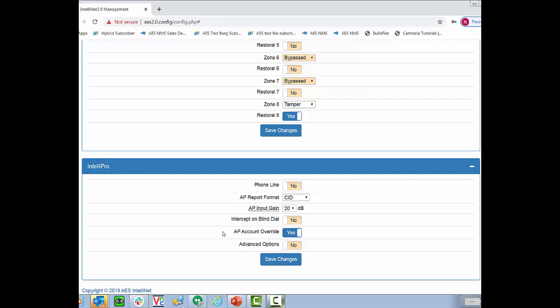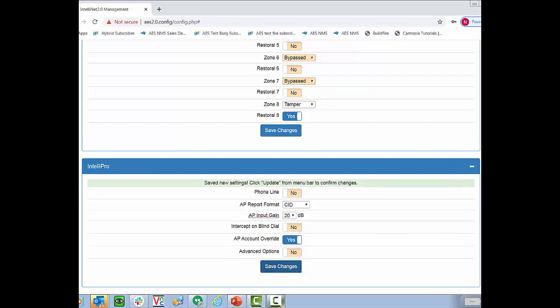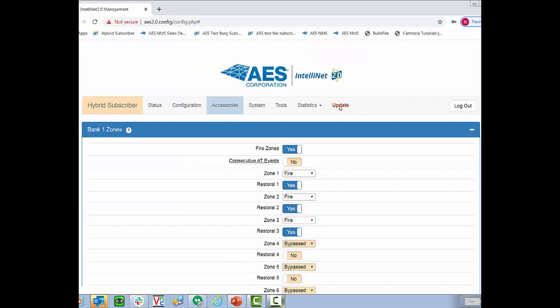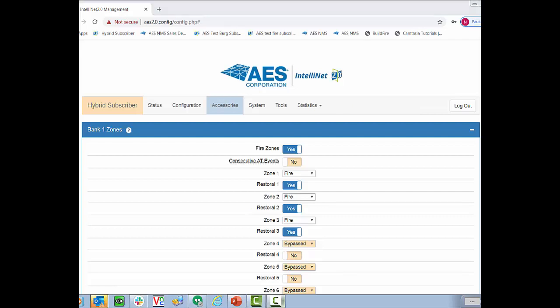So as long as your alarm panel is set to report in CID, you don't actually need to gain access to it to install a subscriber. All you need to do is program into the subscriber what you want, the account ID, and then make sure to hit the AP account override flag, save changes, and then update your radio, and you will be all set. And we're going to hit update to send those changes to the radio. And those are really the few things that need to be changed with every installation.